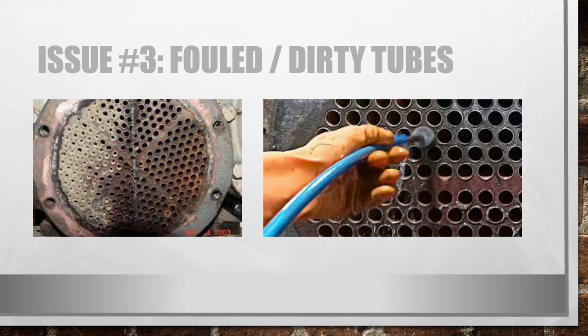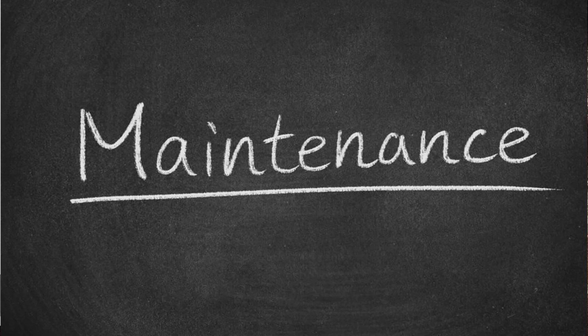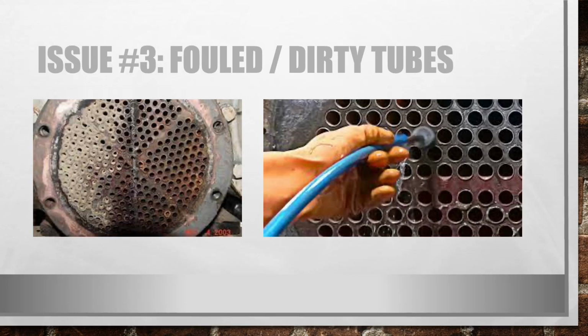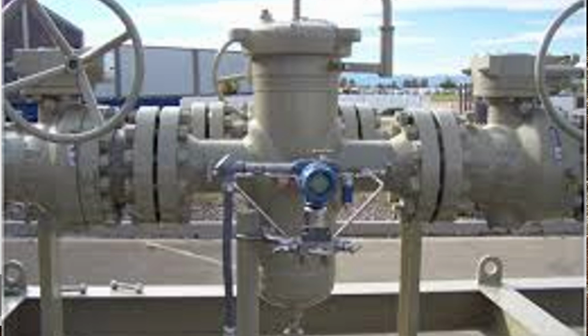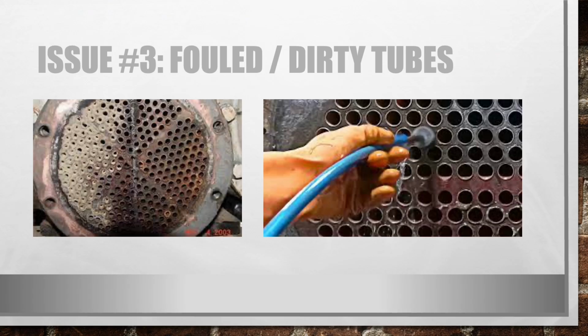So chemical treatment's probably the number one thing. Another thing could be, obviously, lack of maintenance. If they're not punching the tubes regularly, and they should be doing it once a year, that's definitely going to cause the problem as well. Some other things I've seen: missing or rotten screens for the loop strainer. If the strainer's not picking up all the crap that comes through it, all of it's going right into the condenser. And since the condenser is the lowest velocity, everything's going to drop out right in the condenser.